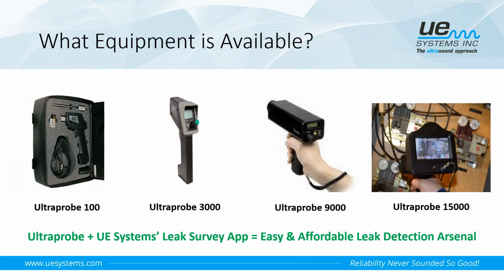So where the first two, the 100 and the 3000, are really what I would consider to be entry-level troubleshooting type instruments, the 9000 would be better suited for multiple applications like bearings or steam traps, because we have the ability to adjust or change the frequency according to what the application is.